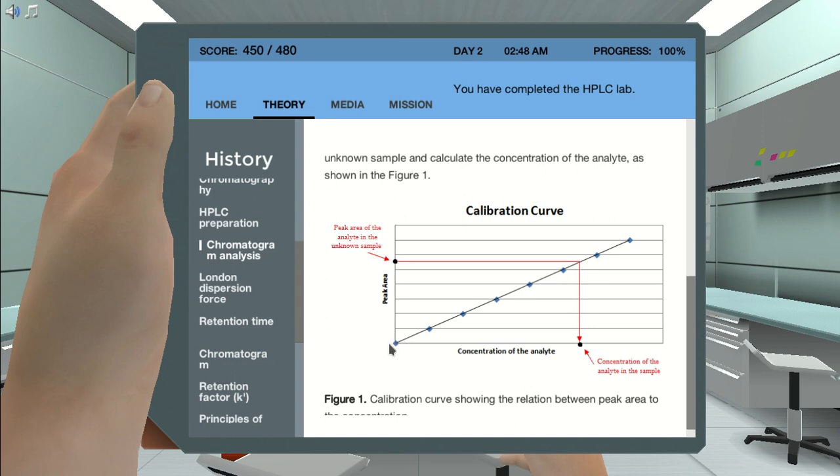When you're done, you take your second sample, your second dilution of the same pure active ingredient. You put that through the machine. It takes a long time, it could take like 20 minutes. Let that go through the machine, it gives a peak, calculates the area under the peak for you, and you plot that on Microsoft Excel. Y is the integration, and X is the concentration that you know because you made a dilution. Your third dilution, you throw it through the machine another 20 minutes, and the machine gives you peak area, and you give Microsoft Excel the concentration because you made a dilution. You keep on doing that, and that's how you get the calibration curve. You're putting these pure samples at different dilutions through the machine one at a time.